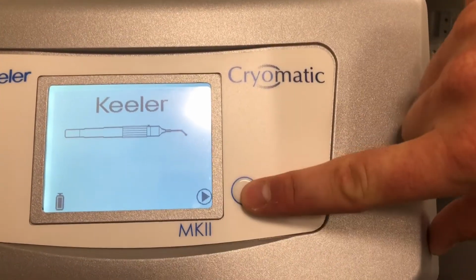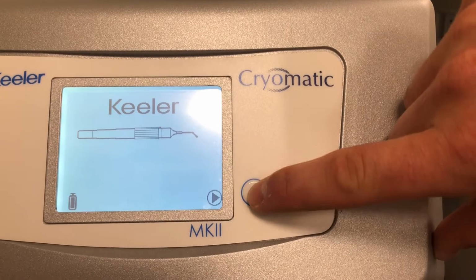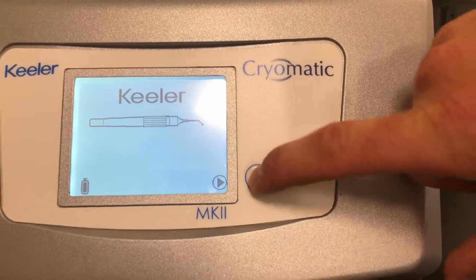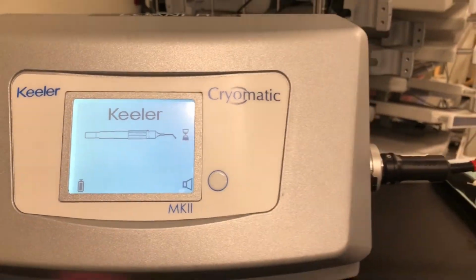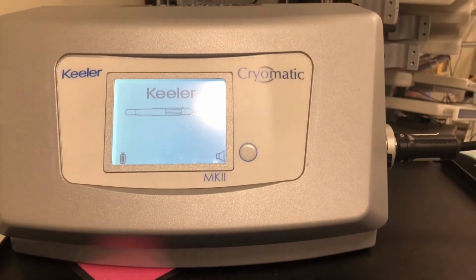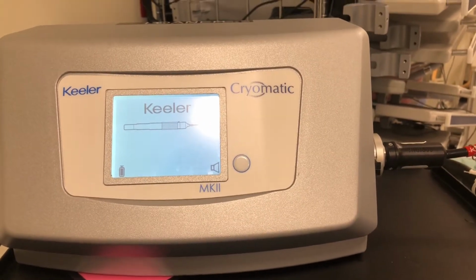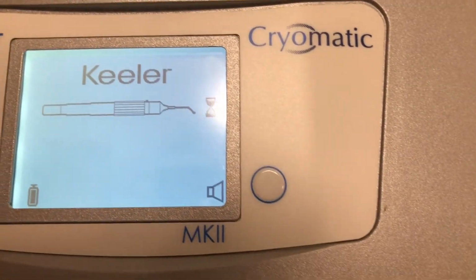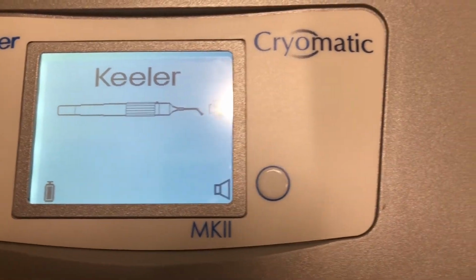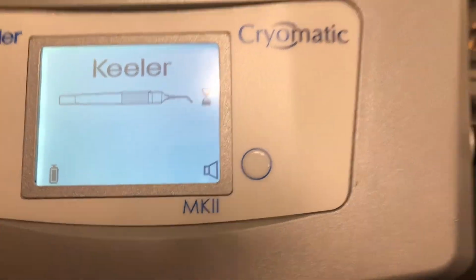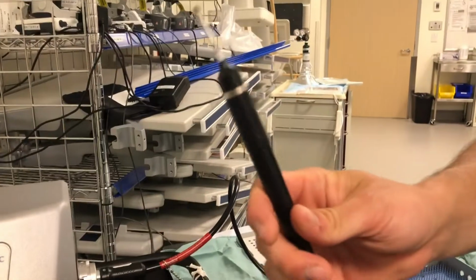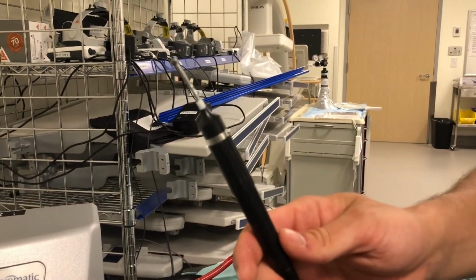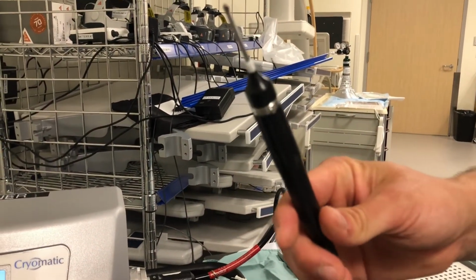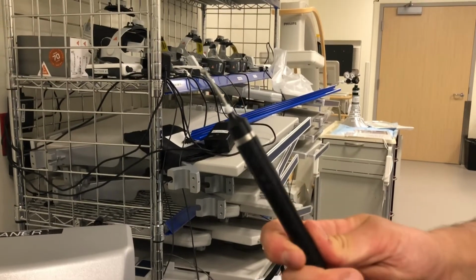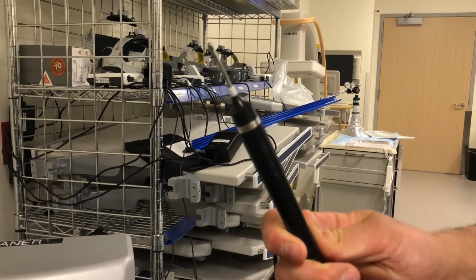We'll then press this button here to prime the probe. And this process takes a while. It takes a full 90 seconds to fully prime. It's also important when you're priming that you don't let the tip touch anything else other than its container or maybe a sterile basin to give you some more room to work, because as it's priming, it might be hard to see in the video, but it'll start frosting over.